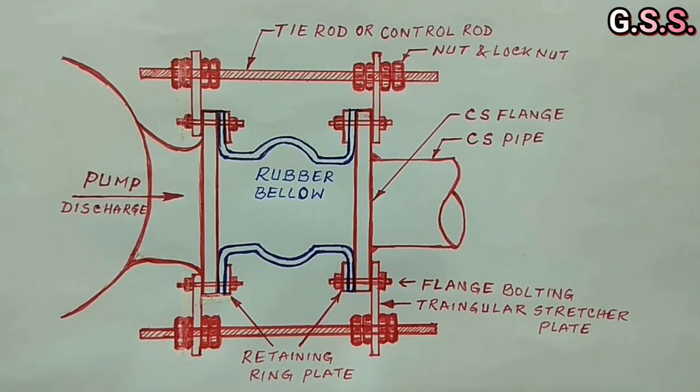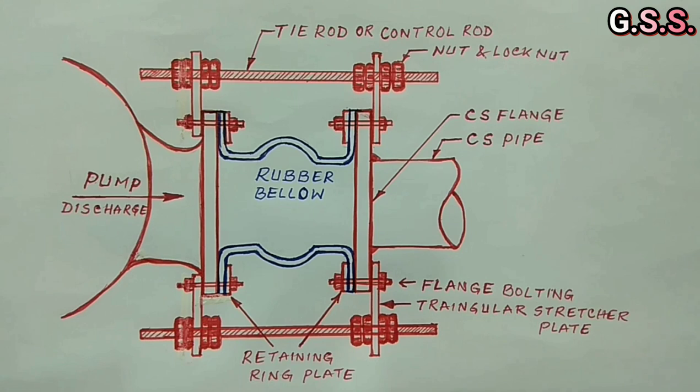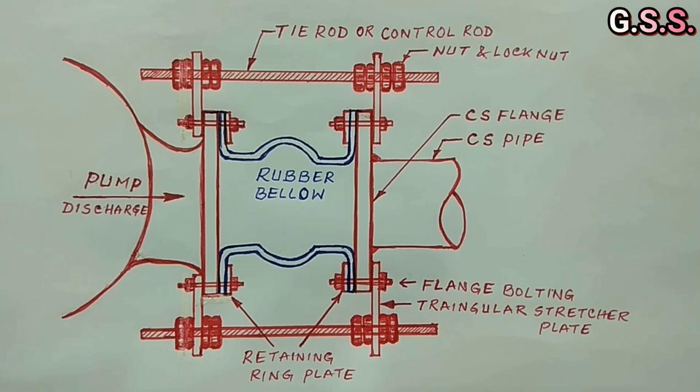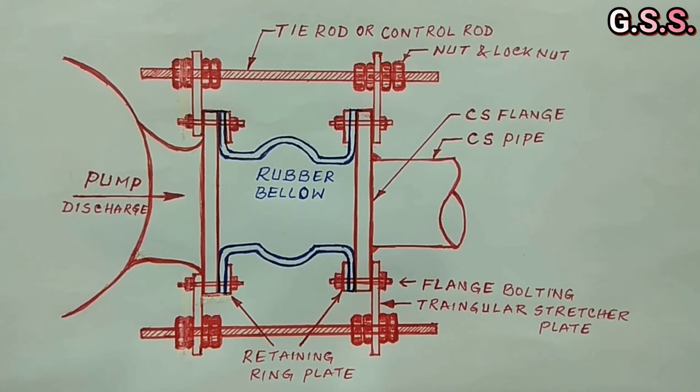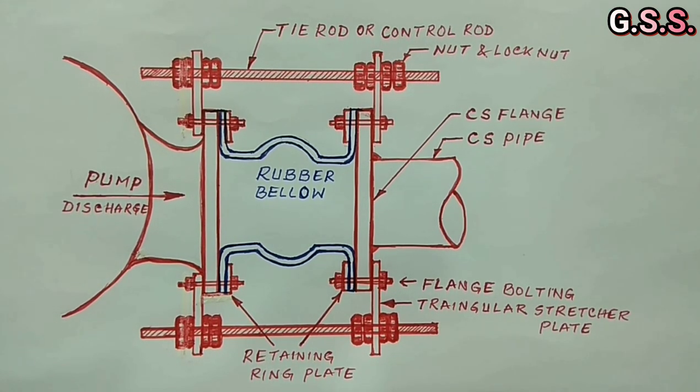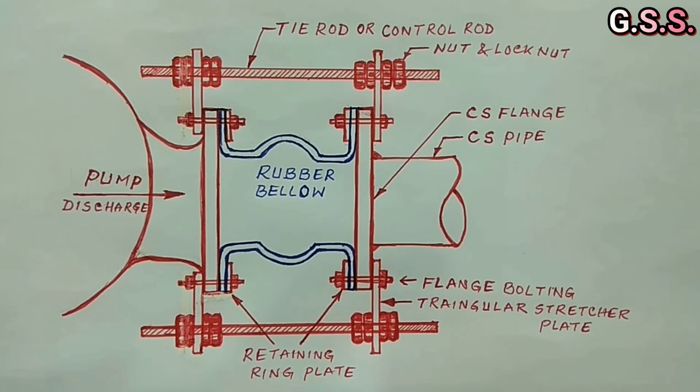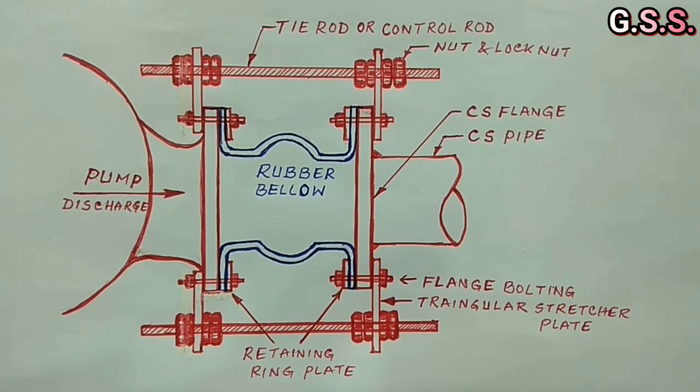This type of rubber bellows are used for non-critical services like cooling water, air, etc. up to 10 bar gauge pressure and 60 degree Celsius temperature. For high temperature and high pressure critical services metallic tied lateral bellows are used.